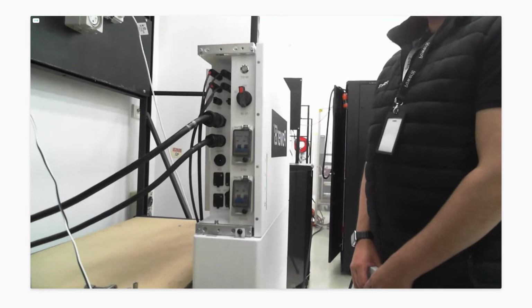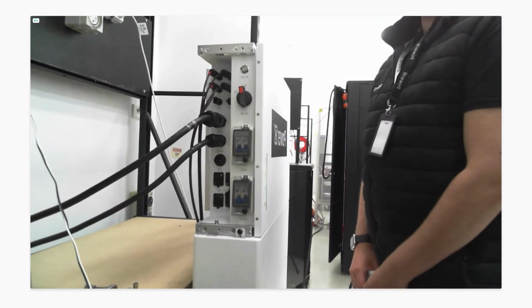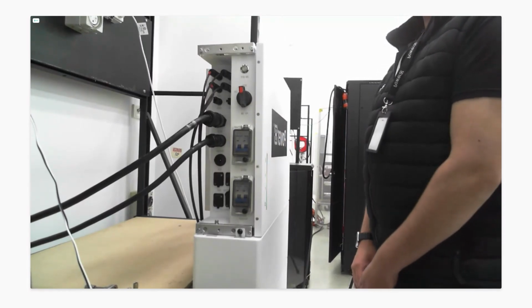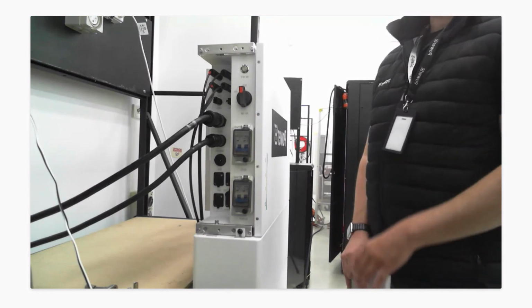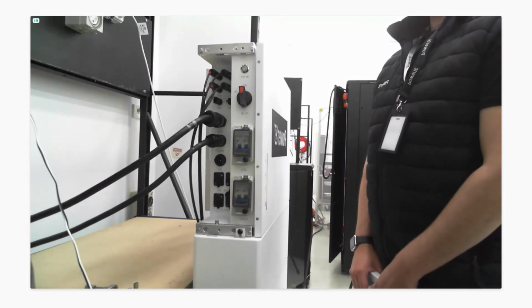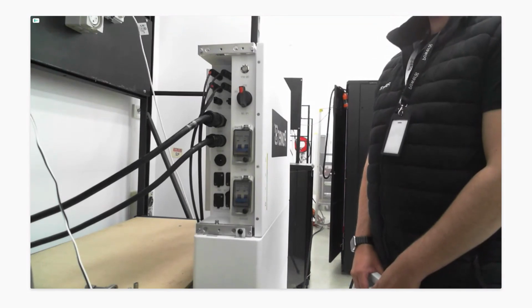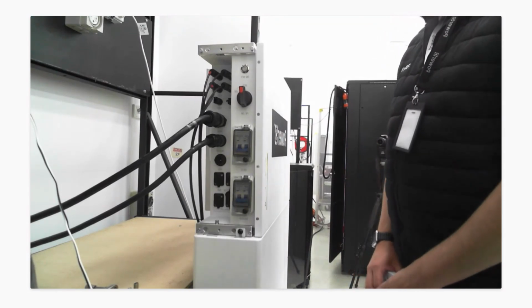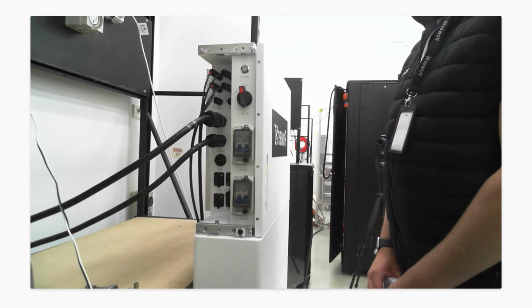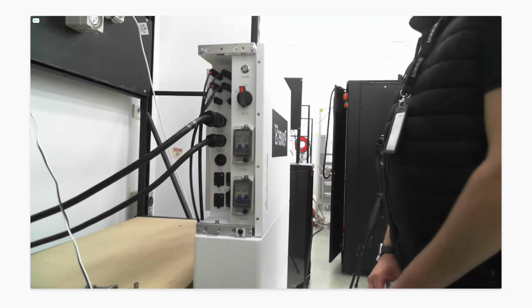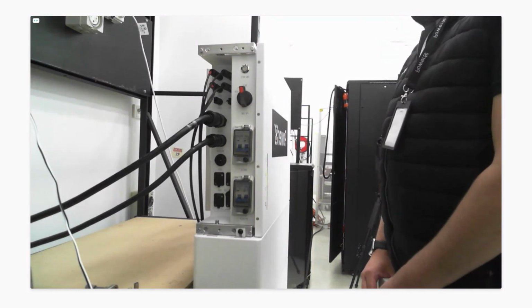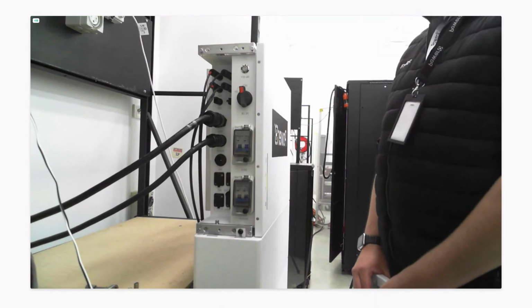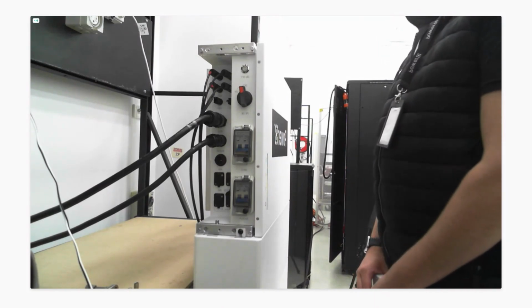Right, but because we're always installing with an associated battery, the limit for STCs is now the manufacturer's recommendation. Because you can have energy going to the battery and being inverted. Correct, because the DC bus is before the inverter. Yeah, so because of that, we can breach that 1.33. And the manufacturer's specification, in this case, what we say is the 200%.